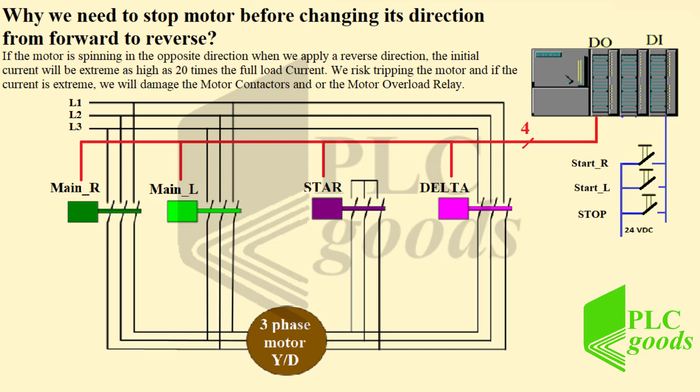While we need to stop the motor before changing its direction from forward to reverse, if the motor is spinning in the opposite direction when we apply a reverse direction, the initial current will be extreme, as high as 20 times the full load current. We risk tripping the motor, and if the current is extreme, we will damage the motor contactors or the motor overload relay.